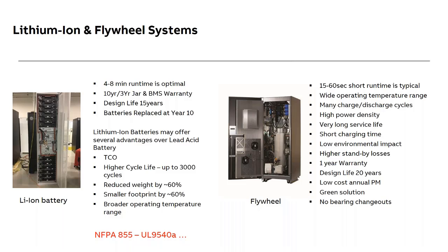from cell to cell. So NFPA 855 pretty much required that if you install a lithium-ion battery, that battery cabinet has to be 3 feet away from anything else, including other battery cabinets and the wall and the UPS. So lithium-ion batteries offer a number of benefits, but mainly a smaller footprint and reduced weight. Pretty good performance also, but with the NFPA 855, the footprint savings was just out the window.